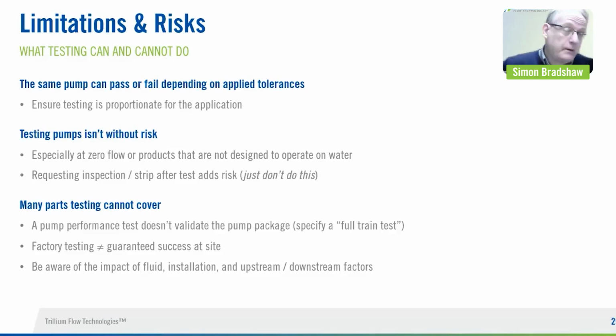Another requirement that unfortunately we see quite a lot is a request to strip and inspect the pump after the test. And I'll be honest, I just think it's generally a terrible idea. It's essentially like striking a match to see if it lights. You've taken a pump that you've proven to be good, and then you're going to take it apart and put it back together again. And now what? You've just put the pump back together. Are you going to test it again?